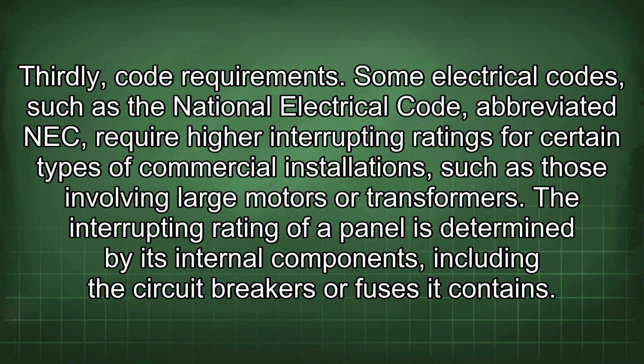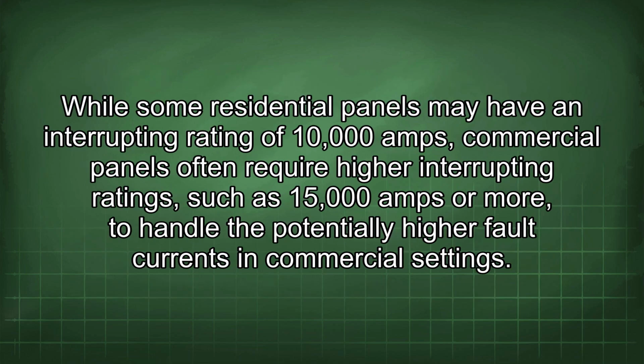The interrupting rating of a panel is determined by its internal components, including the circuit breakers or fuses it contains. While some residential panels may have an interrupting rating of 10,000 amps, commercial panels often require higher interrupting ratings, such as 15,000 amps or more, to handle the potentially higher fault currents in commercial settings.